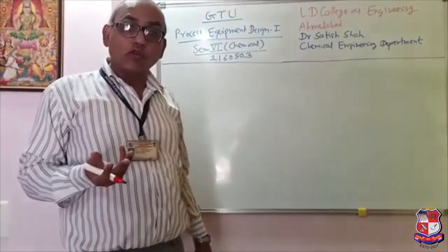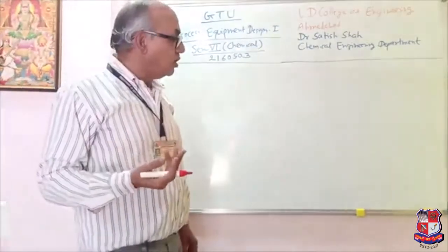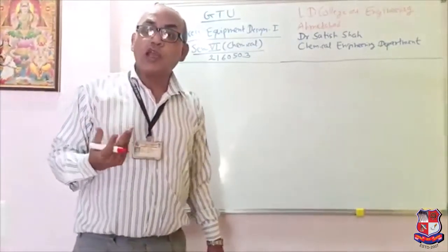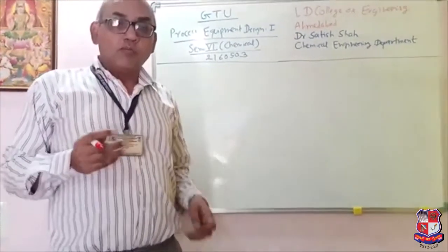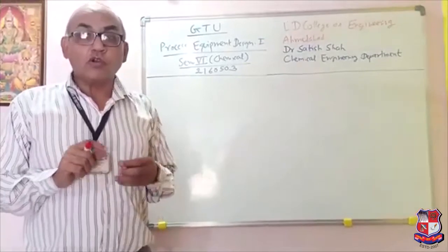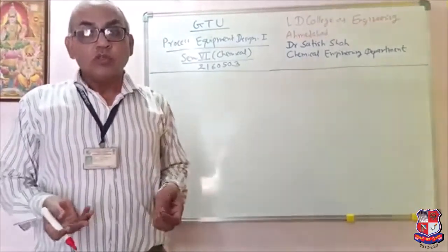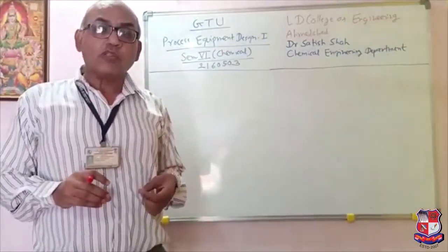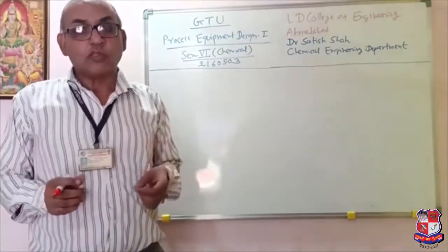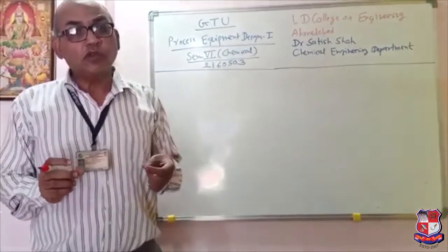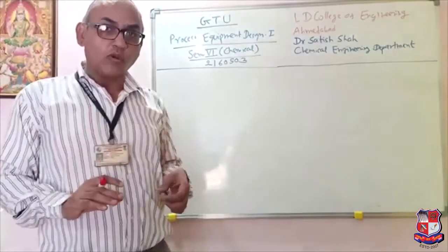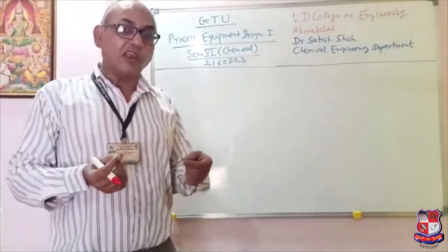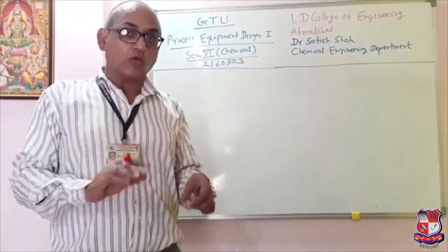Similarly on the shell side, when you find the pressure drop on the shell side is high, what will you do? We know that pressure drop on the shell side is controlled by the baffle spacing. So if you are getting high pressure drop on the shell side, you have to increase your baffle spacing. But remember, when you increase your baffle spacing, your shell side pressure drop will go down, but at the same time your shell side heat transfer coefficient will also go down.